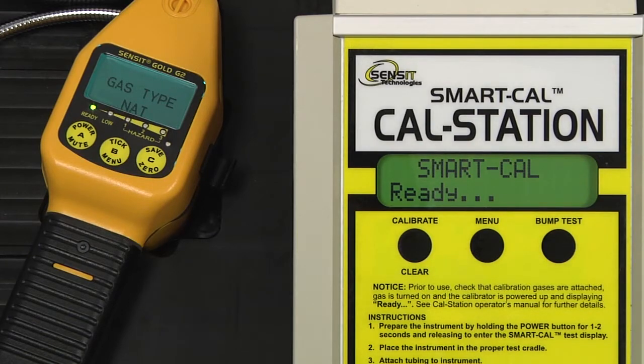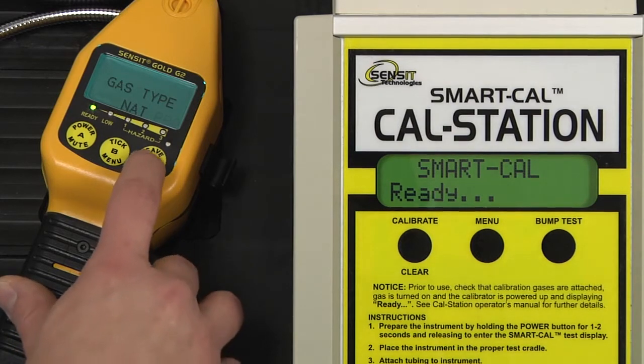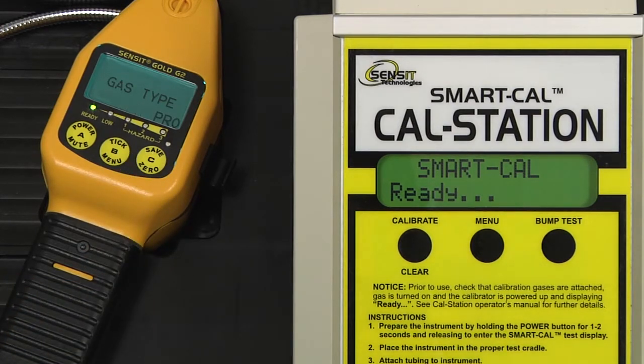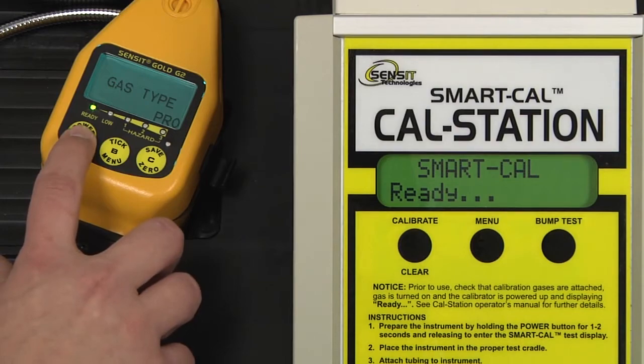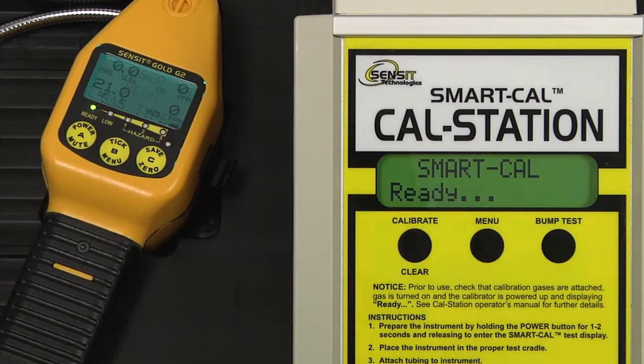and at the bottom of the screen the current gas type selected will be displayed, which is natural gas in this case. If we'd like to select propane, we can press and release the C button, and then exit back to the working display by pressing and releasing the A button. In the upper left, we now have PRO, indicating that propane is the selected gas type, and the cal station will calibrate for that gas.